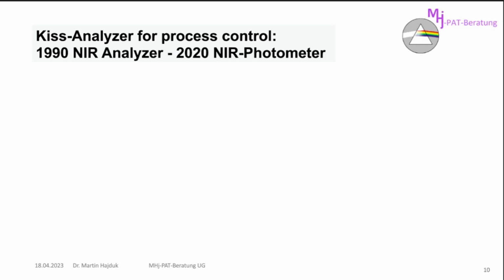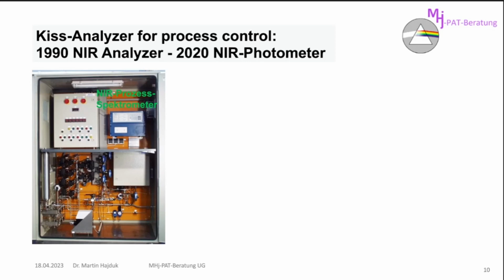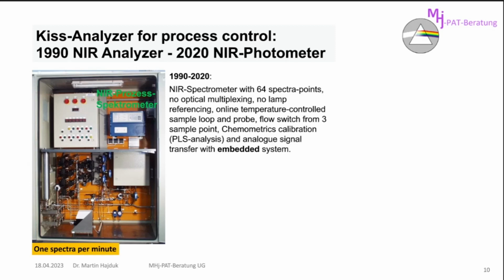In 1990, I installed my first NIR analyzer. This is the blue machine here. This machine can measure an NIR spectrum at 64 spectral points, but no optical multiplexing was possible. So if we want to analyze, in this case, 5 sample streams, we have to switch the fluid. These are 5 valves inside the sample cell, installed inside this cabinet, because we can't measure the temperature, or we can't calculate the influence of the temperature. We tempered the sample inside this cabinet.